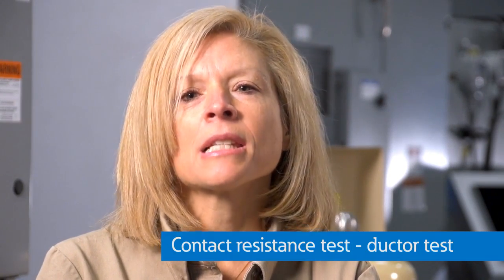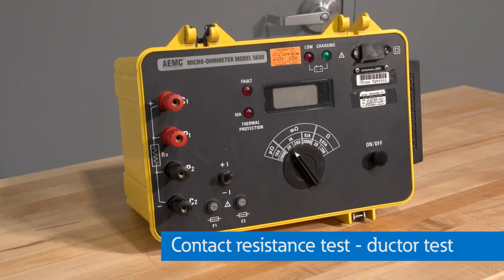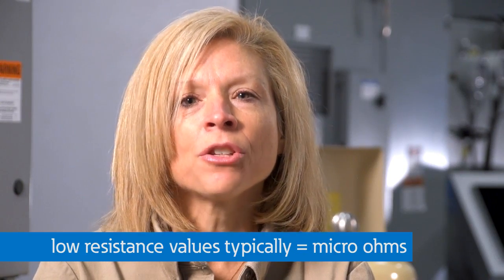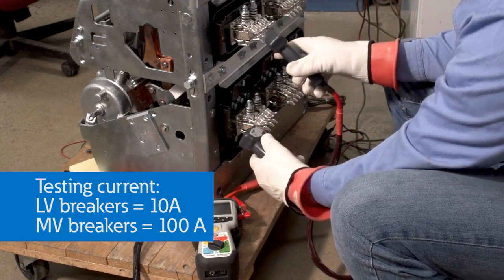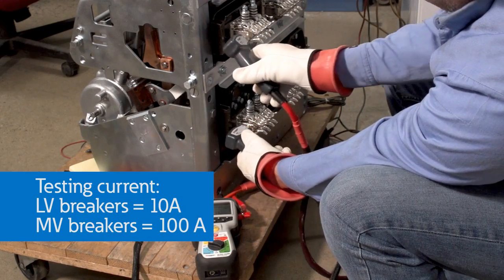While a Megger test is done to check for large values of resistance on insulation, a contact resistance test or ductor test is used to measure low resistance values between any two conductors or electrical connections, such as circuit breaker contacts, cables, or bus bar connections. For this test, you want a low resistance.